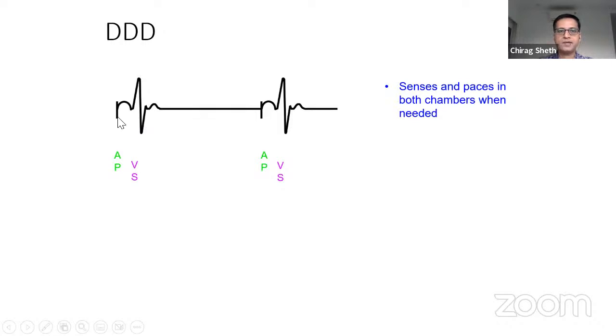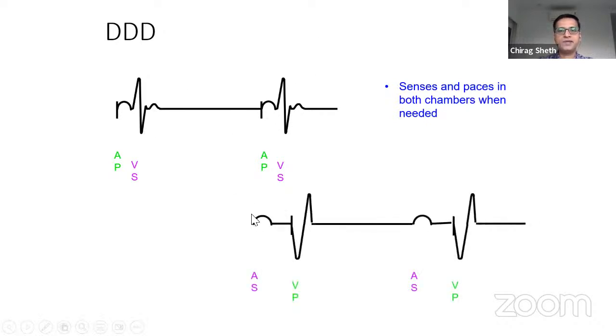So one can have a DDD function like this, where it paces in the atrium but senses in the ventricle. And this is another example where you have atrial activity but no ventricular activity. In that case, it senses the atrial activity and gives pacing only in the ventricular channel. So this is how a DDD pacemaker would work.